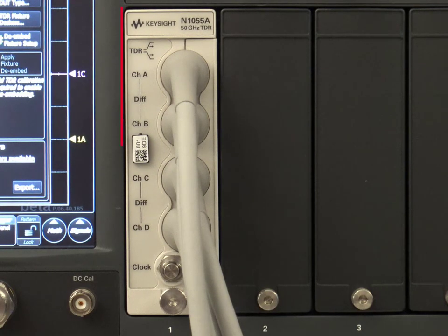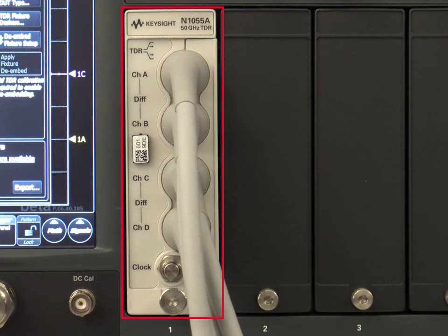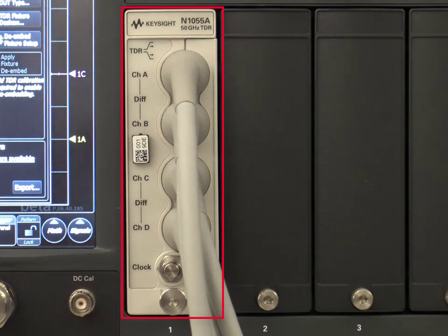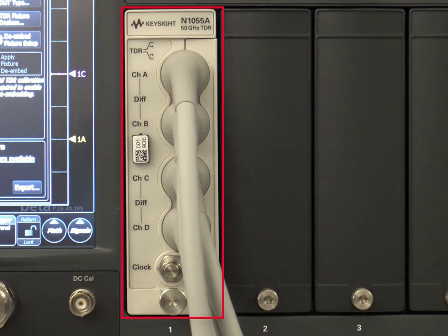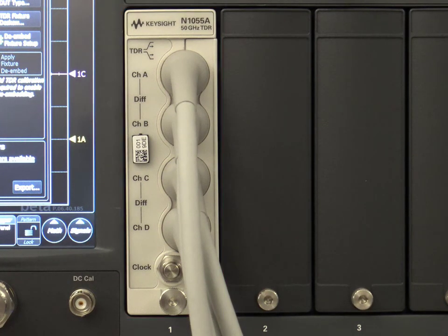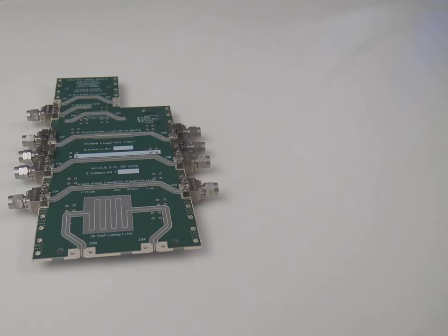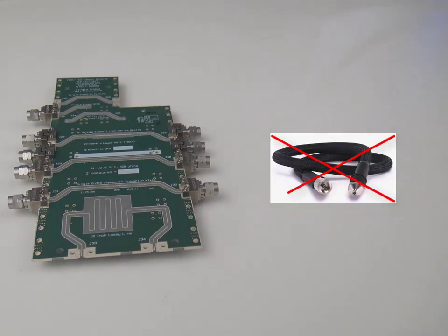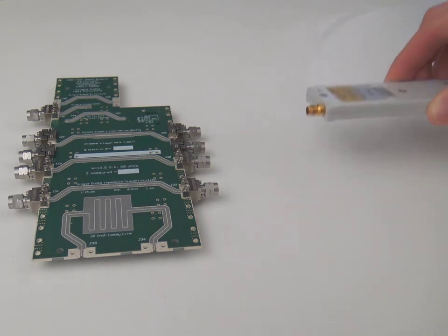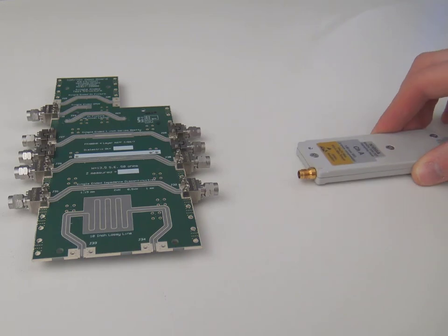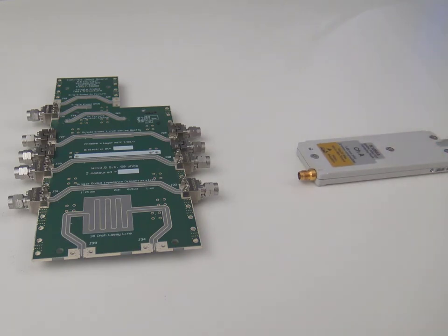Here is the N1055A TDR plus electrical remote sampling heads. A convenient piece of hardware which eliminates the need for connector cables by bringing the measurement equipment to the device under test.